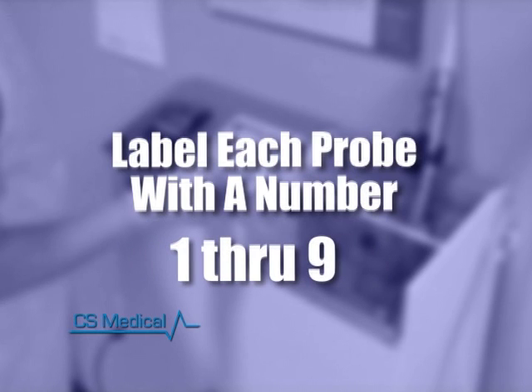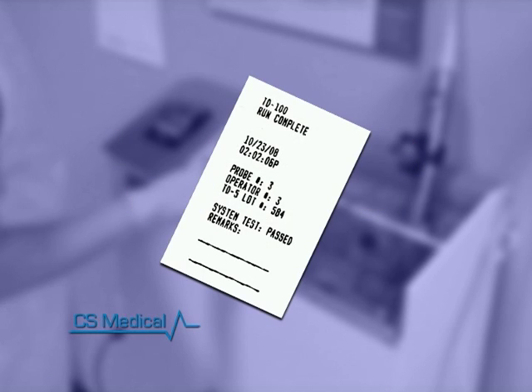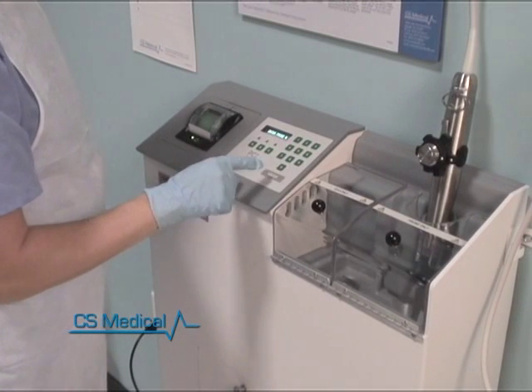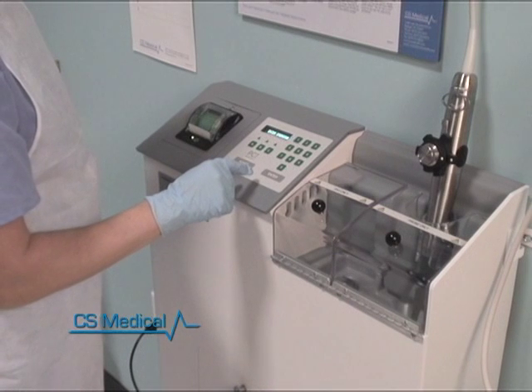Next, you will be asked for the probe number. Many organizations have multiple probes. CS Medical recommends that you label each probe with a number, starting with 1, and continue with each probe up to 9. This number will be entered into the microprocessor and become part of the printed receipt upon a completed cycle. Enter the number 3 for this probe and press Enter.